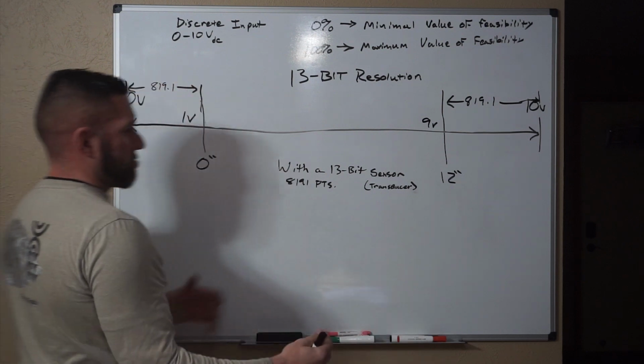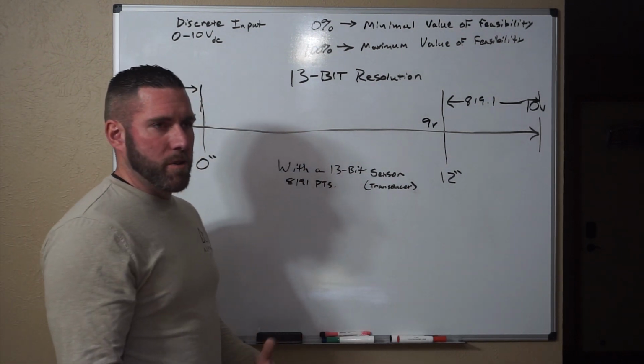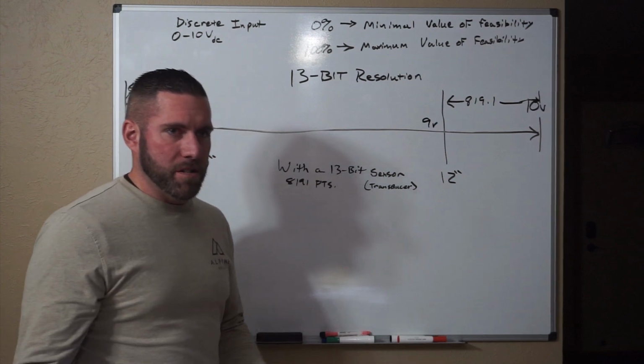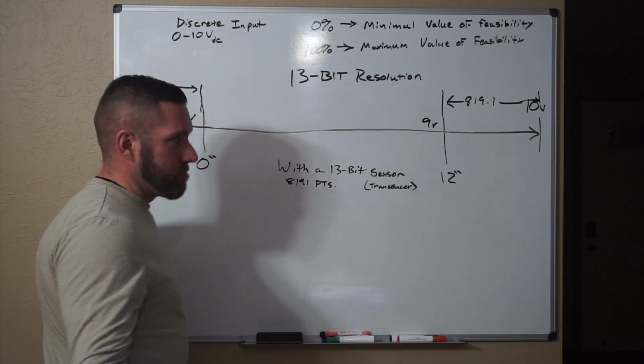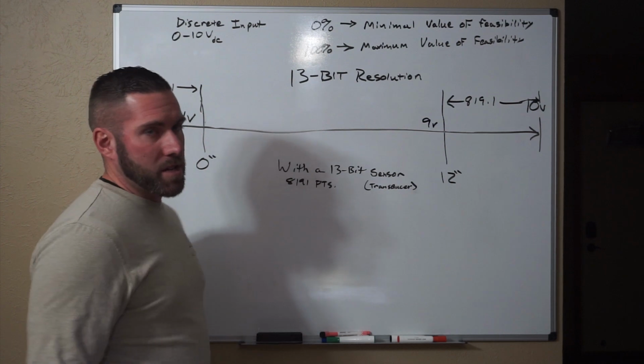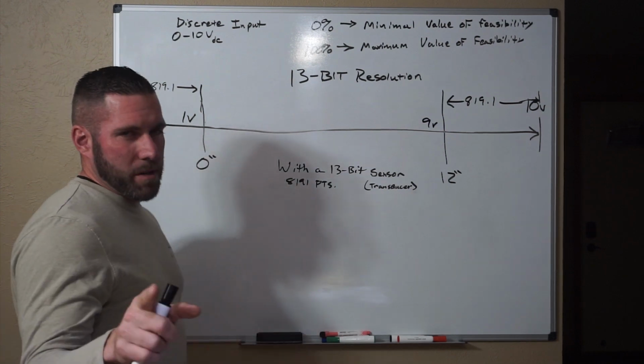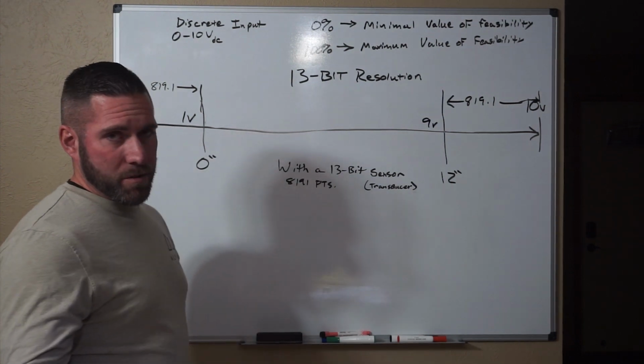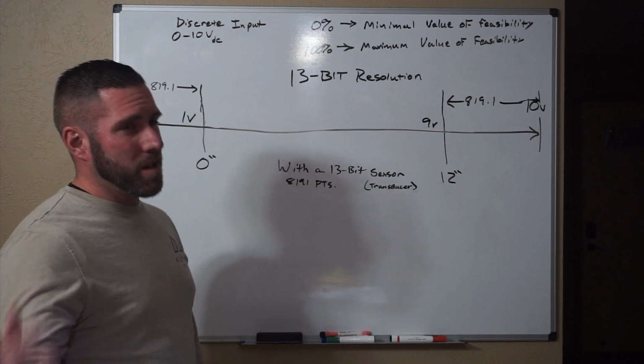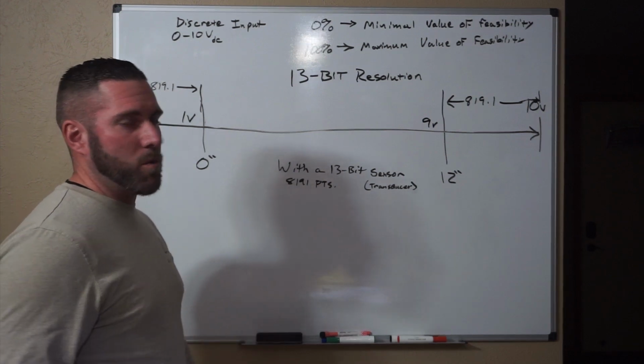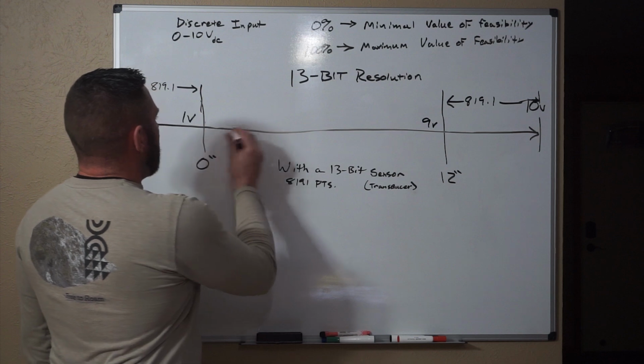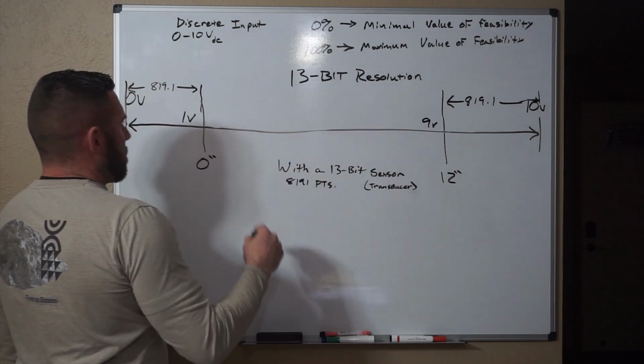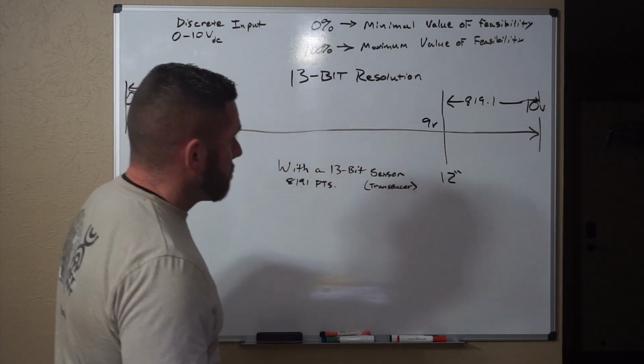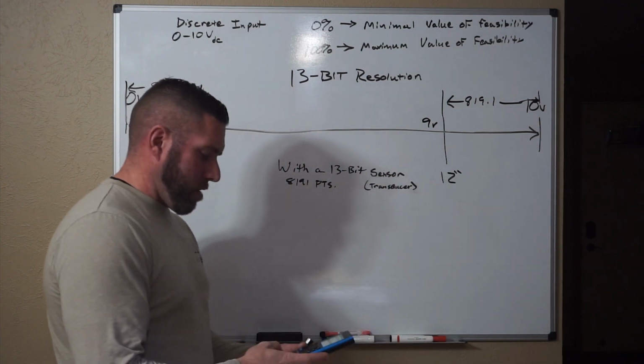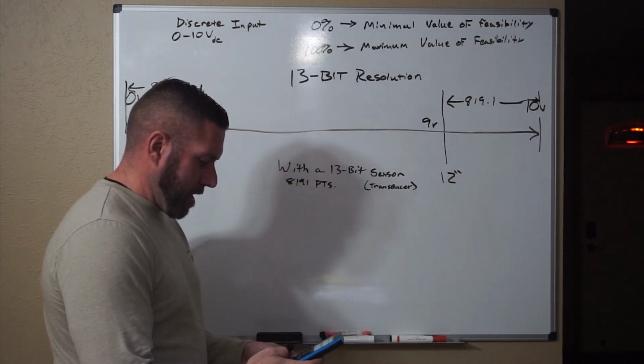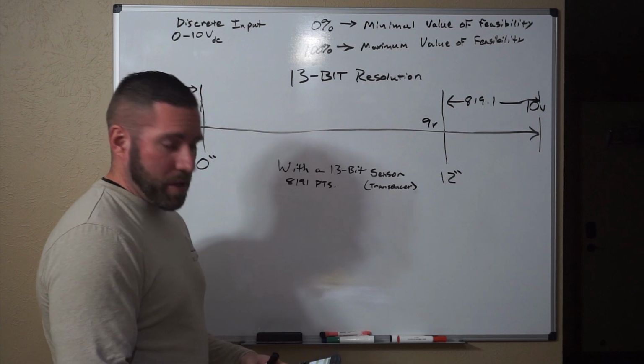If this transducer comes back and it's a little bit out of range, that's okay, as long as it passes calibrations, the NIST ones, not hooking it up to a multimeter. And we'll get into why multimeters shouldn't be trusted, especially the Fluke 289 for 700 bucks. It doesn't actually do automation that well. Okay, so we have 819.1 over there and over there. So now what we need to do is figure out how much range we have in between.